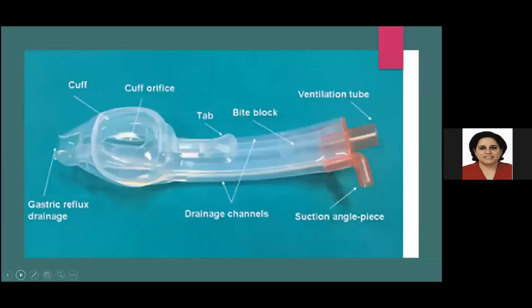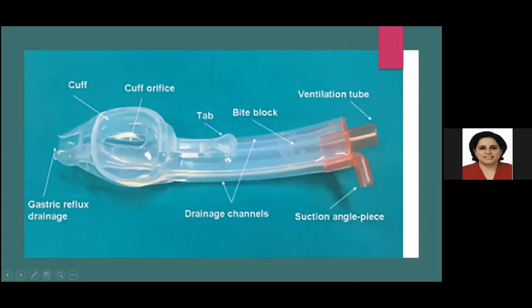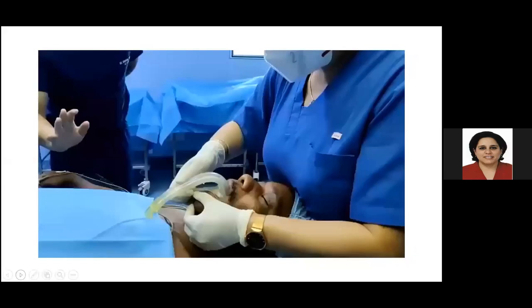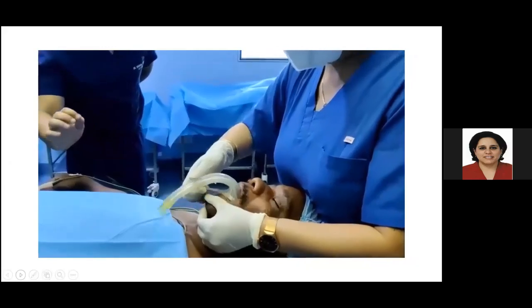I'll show you the picture of the airway device. Here it is. This is the ventilation tube, and the two gastric suction tubes. This is the 90 degrees suction angle piece. These are the bite blocks. This is the tab, which will be better understood on the video. This is the self-sealing membrane. This is the cuff, the small-sized orifice, and this is the large gastric reflux drainage system. So this is the tab which you can pull. As you can see, I pulled it to change the curve of the device to make it easier to insert.